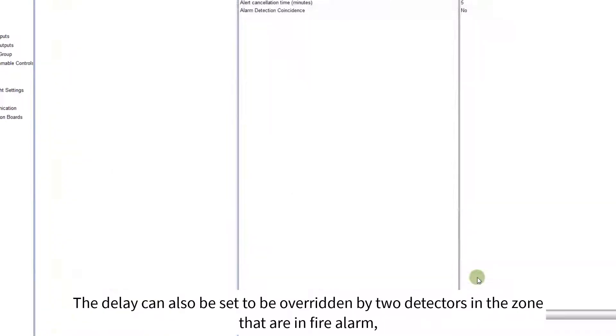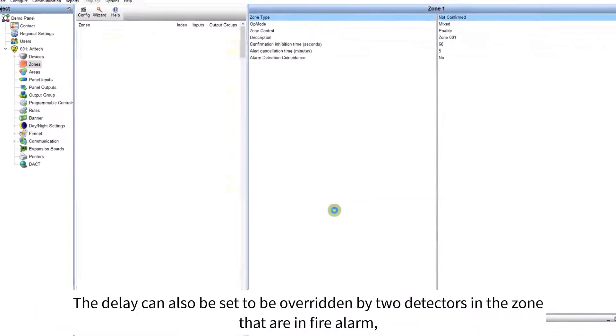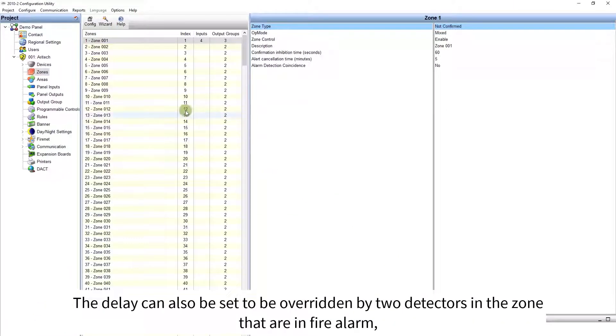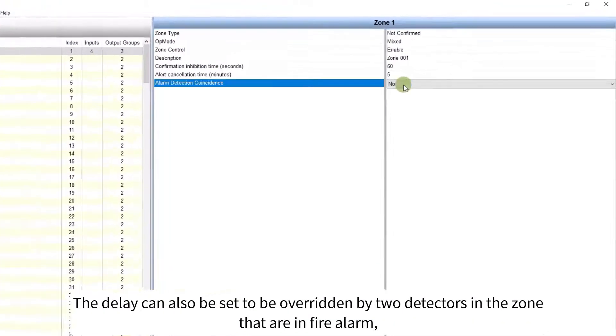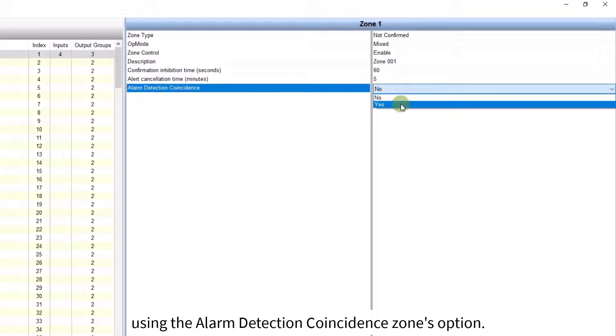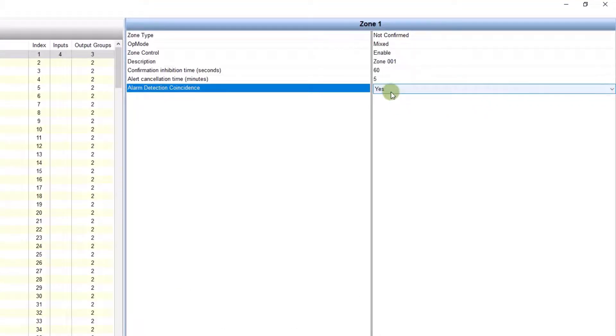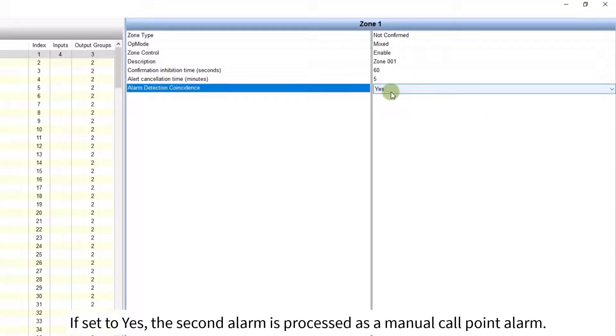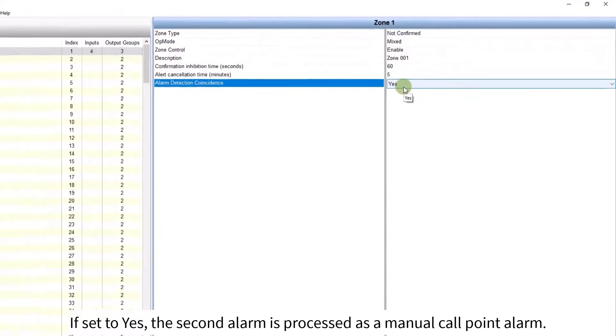The delay can also be set to be overridden by two detectors in the zone that are in fire alarm, using the alarm detection coincidence zones option. If set to yes, the second alarm is processed as a manual call point alarm.